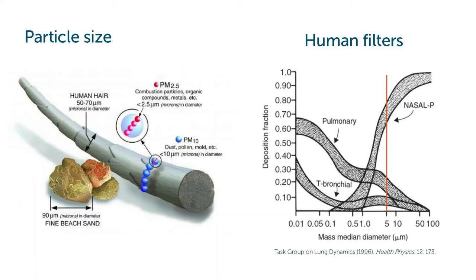Particles are measured in microns. When it comes to filtration, we're worried about sizes that can be inhaled and have biological impacts. These tend to be the particles under 10 microns in size. You can see particles that are approximately 5 microns in size and larger. Most of them are captured by the nasal passages, which explains why your snot can be black when you've been around a lot of smoke or dust.